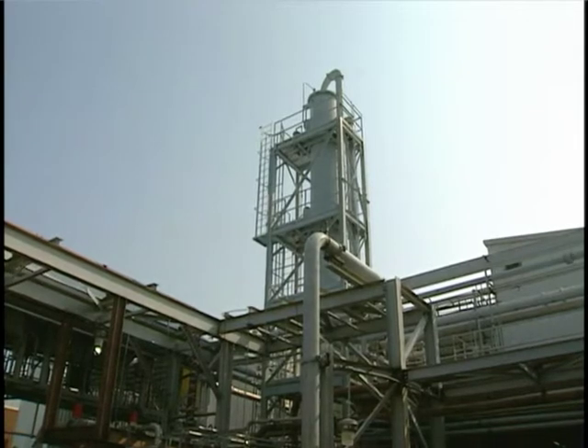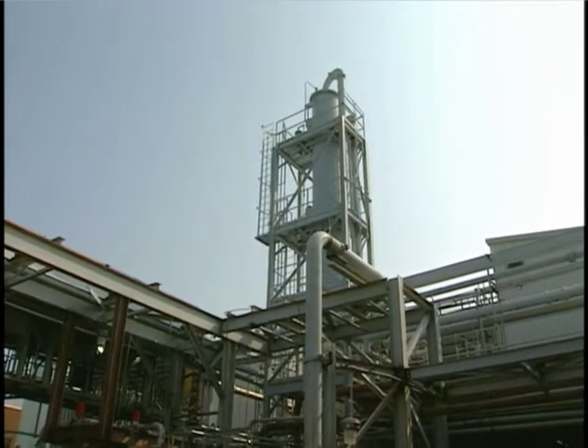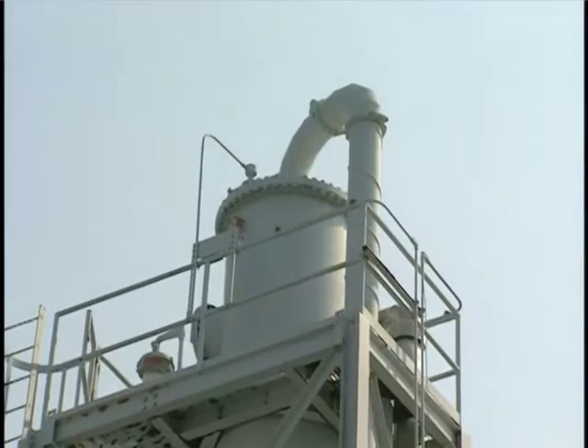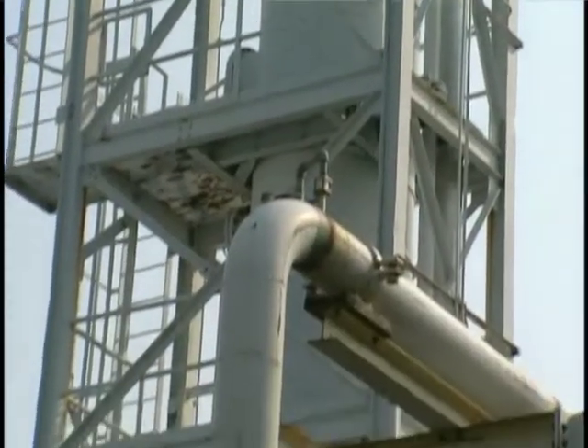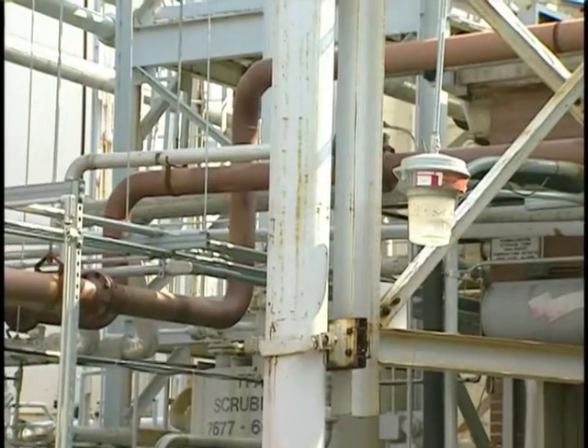Like spray towers, packed beds are classified according to the relative direction of the gas and liquid flows. In the counter-current design, the liquid is introduced at the top of the tower using sprays or weirs and flows downward over the packing material. The contaminated gas stream enters at the bottom of the tower and flows upward through the packing. Because of limitations in the amount of liquid that will move downward against the upward gas flow, this orientation is susceptible to plugging when the concentration of solid particles is high.